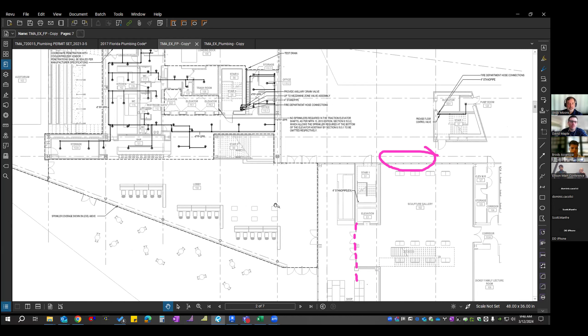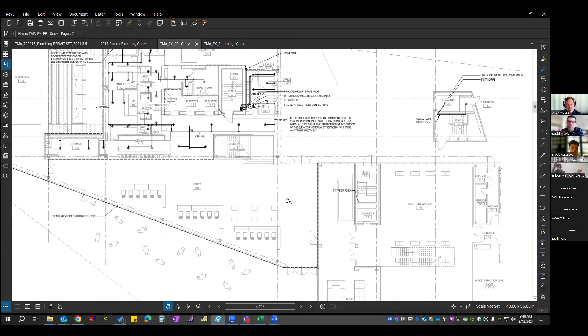This avoids us from having to have a 3-story connection and having to exfiltrate the air and smoke. But it does mean it's compartmentalized, so there could be a fire alarm event on the east side of the building, the existing building, and the sprinklers could be engaged, but it wouldn't trigger the west side of the building. So it's a programming item, but the two buildings operate separately from a fire alarm, fire prevention standpoint.